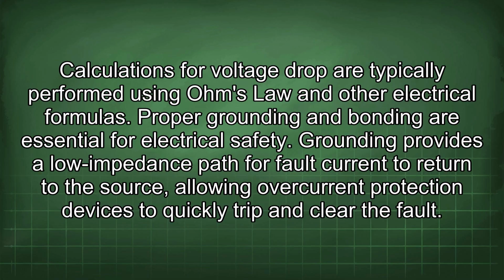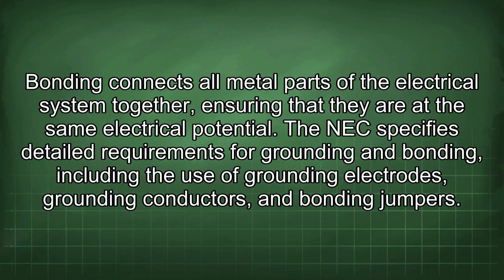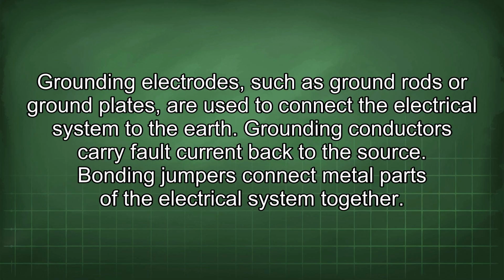Proper grounding and bonding are essential for electrical safety. Grounding provides a low impedance path for fault current to return to the source, allowing overcurrent protection devices to quickly trip and clear the fault. Bonding connects all metal parts of the electrical system together, ensuring that they are at the same electrical potential. The NEC specifies detailed requirements for grounding and bonding, including the use of grounding electrodes, grounding conductors, and bonding jumpers. Grounding electrodes, such as ground rods or ground plates, are used to connect the electrical system to the earth. Grounding conductors carry fault current back to the source. Bonding jumpers connect metal parts of the electrical system together.